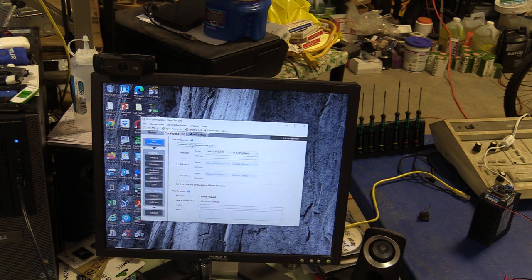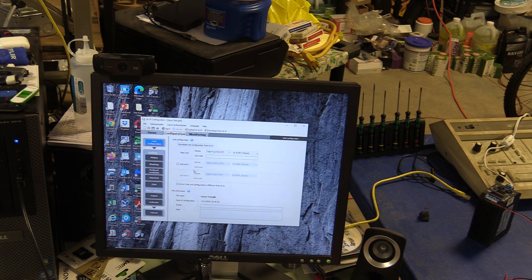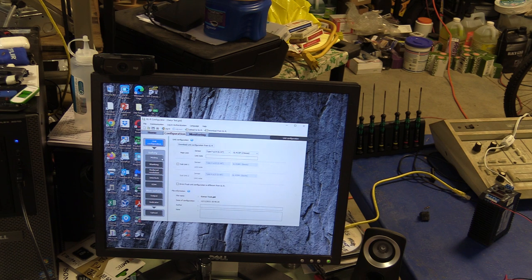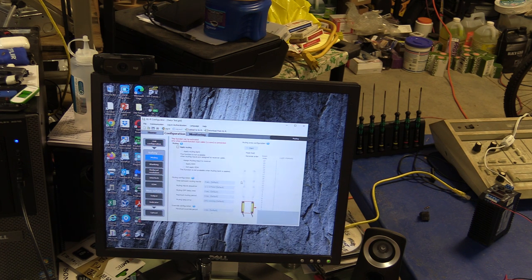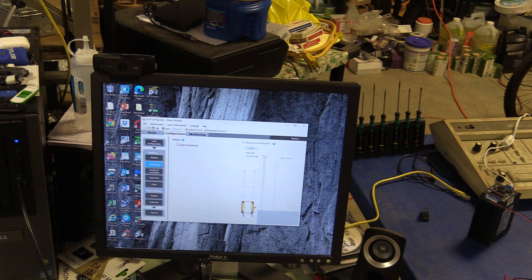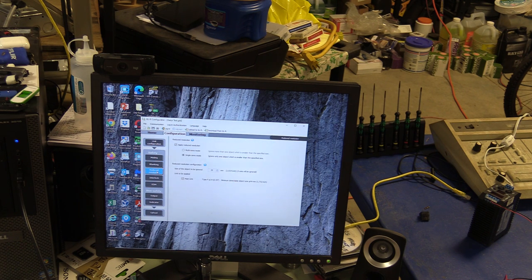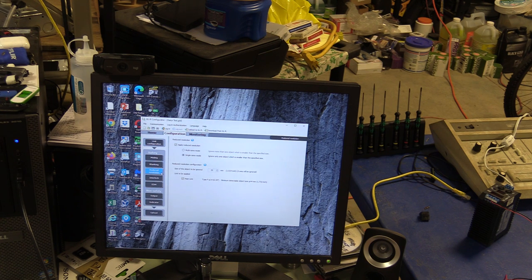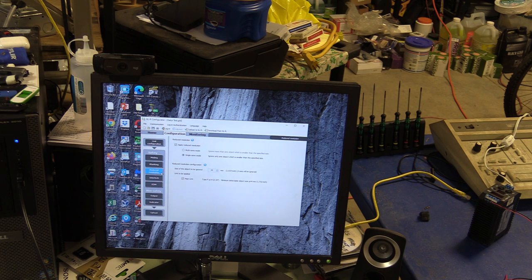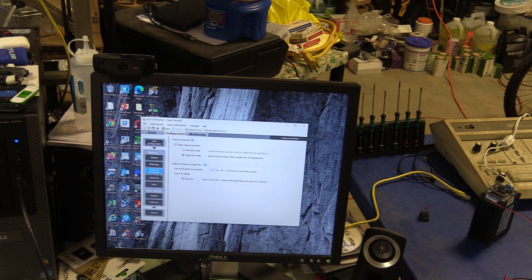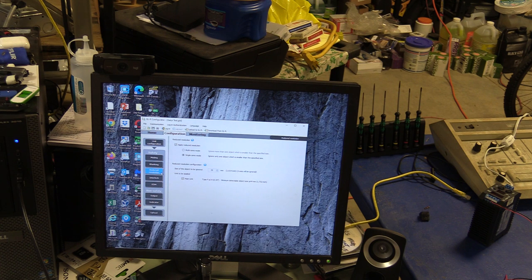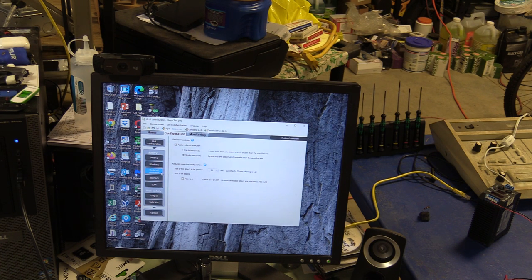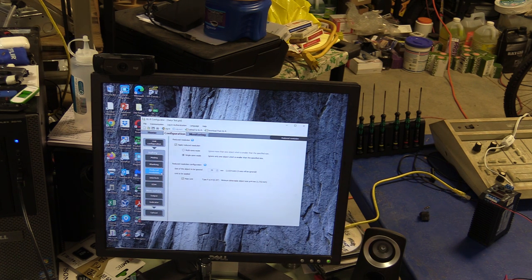We can have multiple ones, so we can hook them together. There is muting. As you can see here, if you have multiple ones, there is blanking. There is reduced resolution, which means you can physically set the size of a diameter—something that you can put in, say maybe a hose or a finger or a piece of wire—and you don't defeat the safety of your machine.